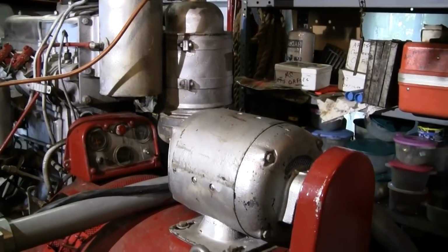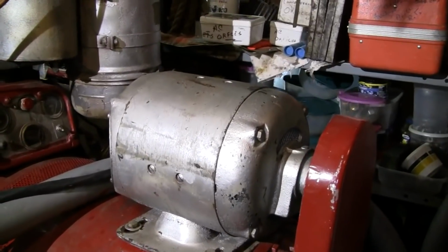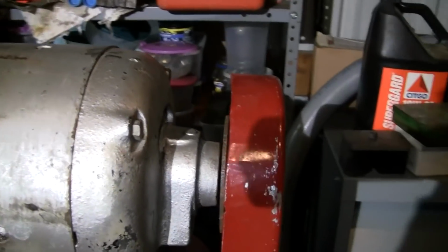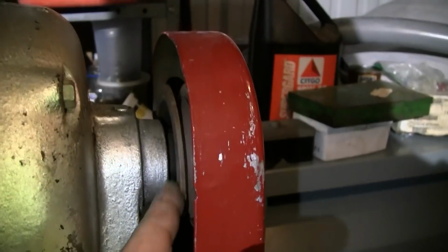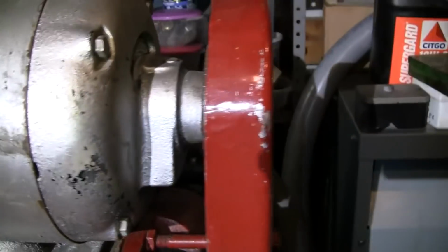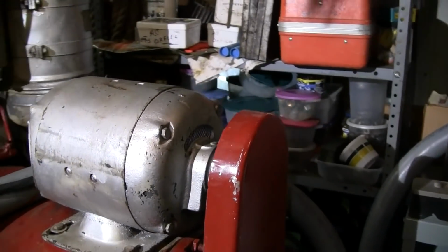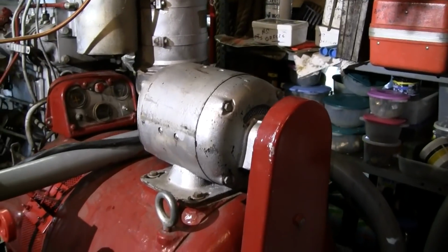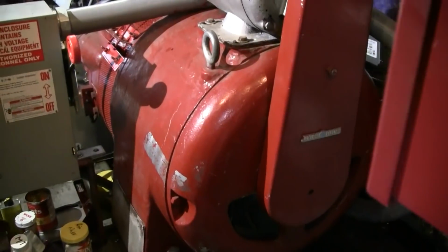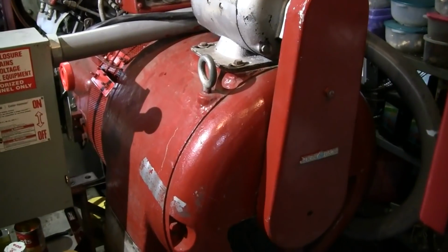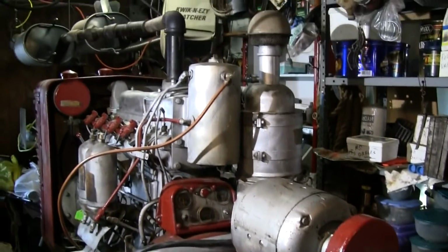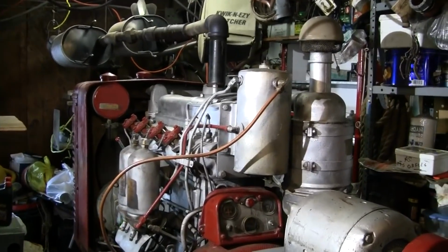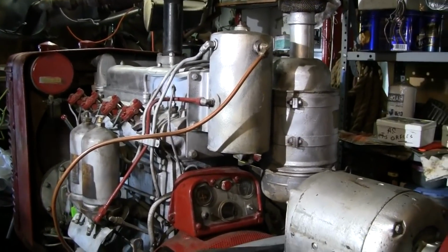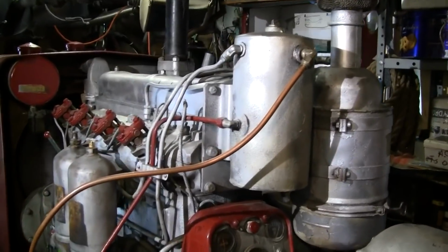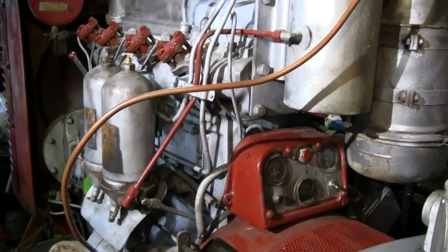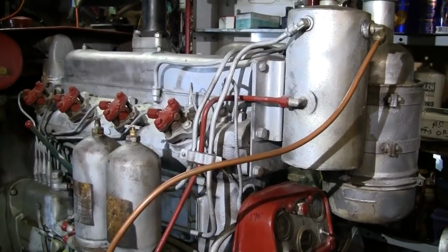I don't know if I mentioned this yet, but this little exciter generator up top is no longer in service. We don't need that exciter because the new electronic regulator can provide the DC to the field from the AC output of the main generator. Let's let it run here at 50% load, let it warm up, and then we'll bump it up a little bit. We'll make it work. It's been a long time since this engine did any work.